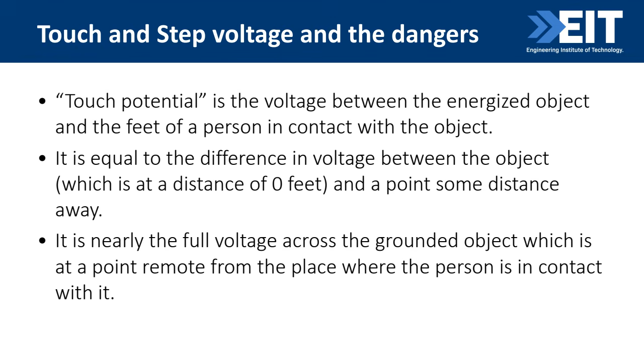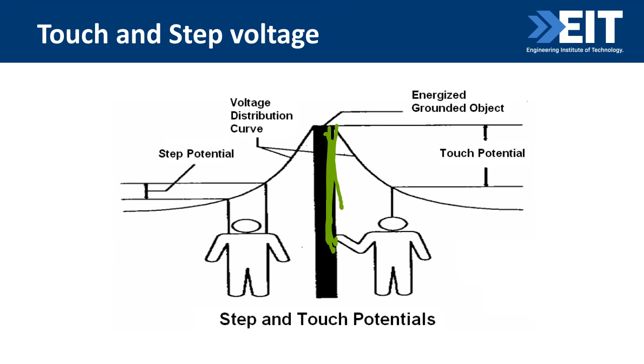Here's a touch potential. So here's a structure here, and that's the voltage going down, down, down. And the step potential is the voltage between your two feet. So if you're standing one foot there, one foot there, you have a step potential. And obviously touch potential could be far greater - you're touching that and you're on some surface, and of course you will then have a touch potential. So those are the two.